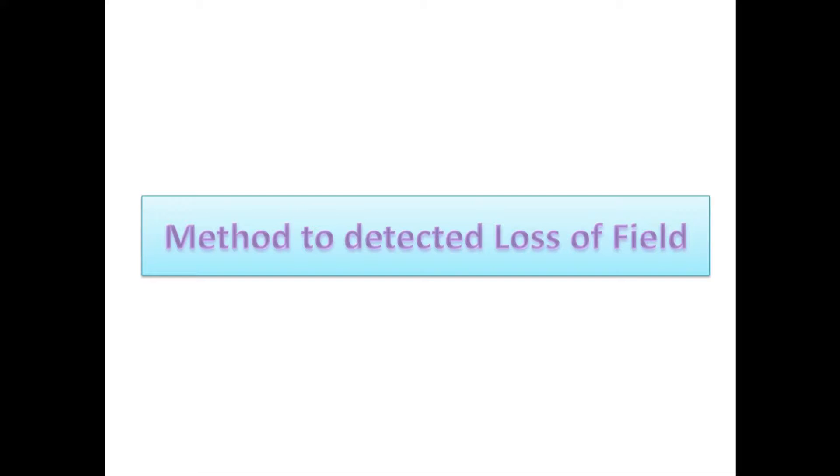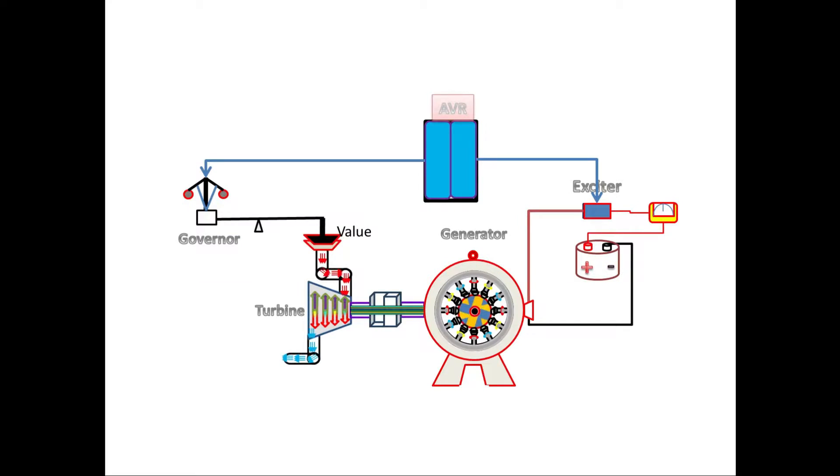Now, we will see what are the ways to find the loss of field while under excitation occurs on generator. First, it is very easy method to detect the loss of field is to check the field current. If the magnetic field is produced on the rotor due to exciter, then definitely there will be a current flow on it.